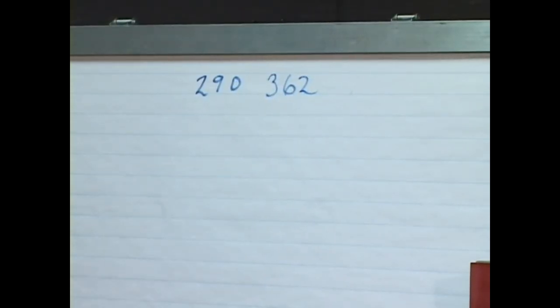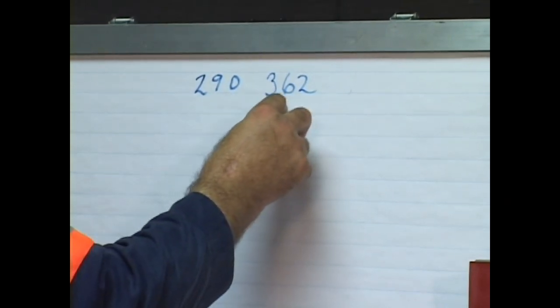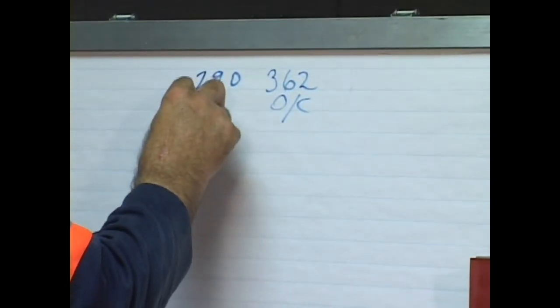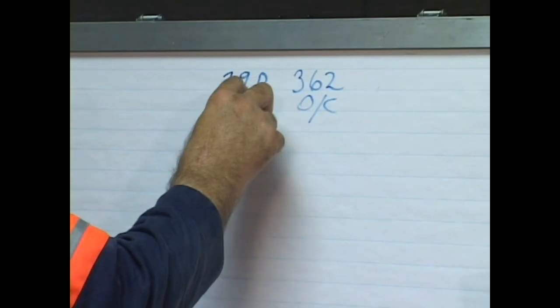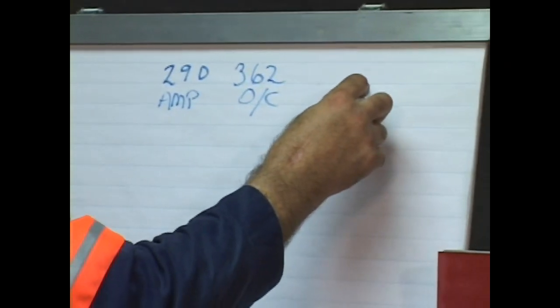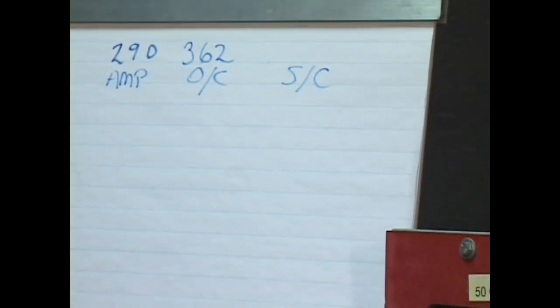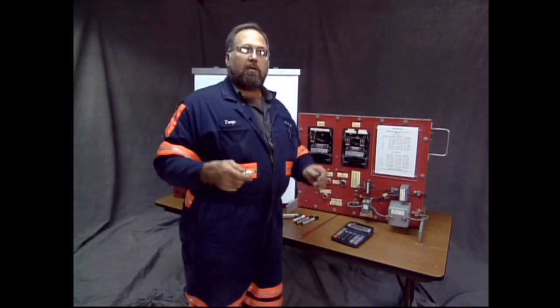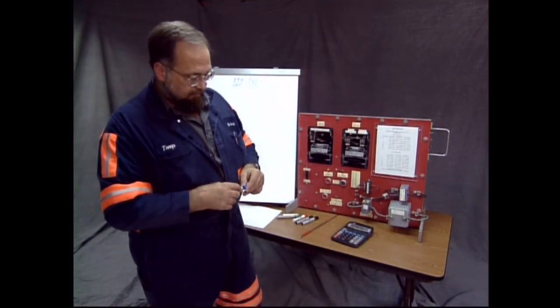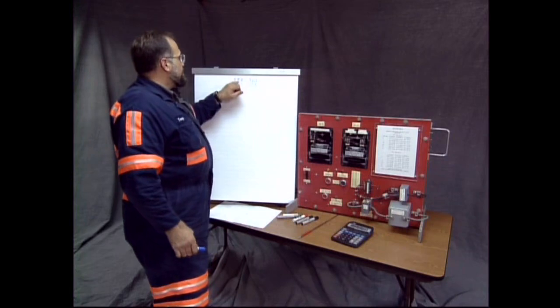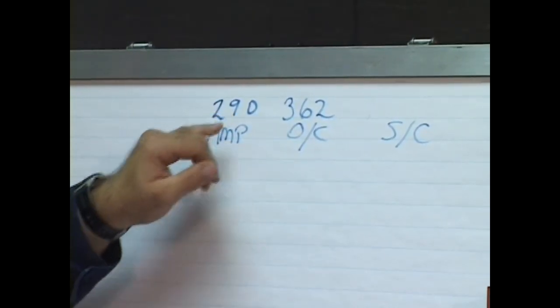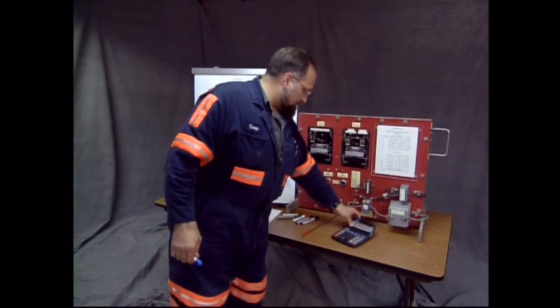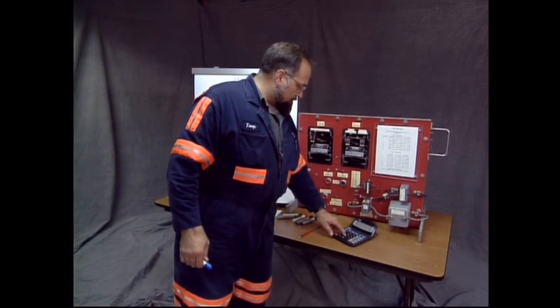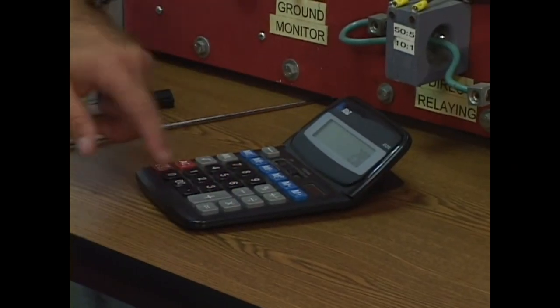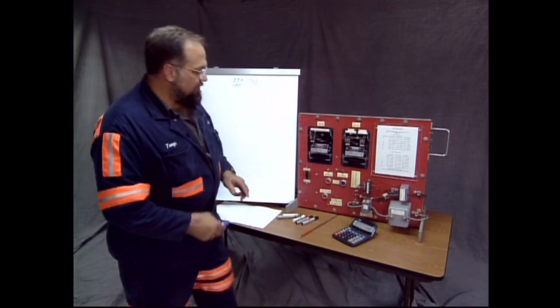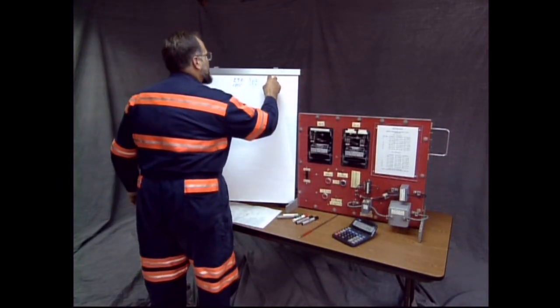That's the overcurrent setting. I'm going to mark that as OC. And this one here, I'm going to call that ampacity. Now the next one that we need would be short circuit. Okay? Short circuit, 600% of the ampacity. 600% of this, not the overcurrent setting, but of this. So it would be, using our calculator here, 290 times 6. And that equals 1,740 amps. 1740.